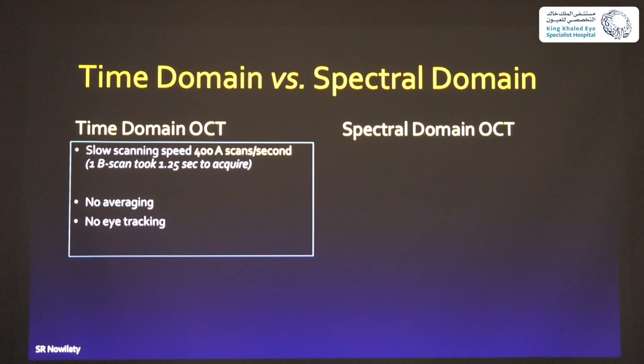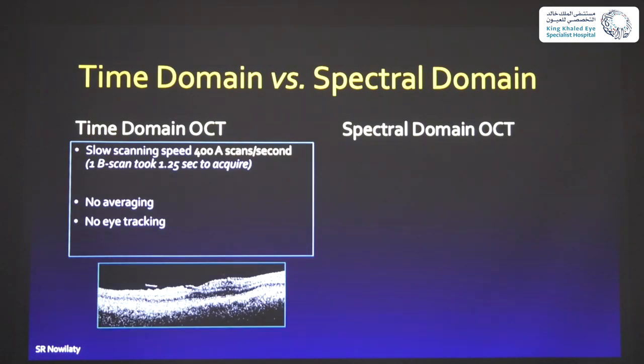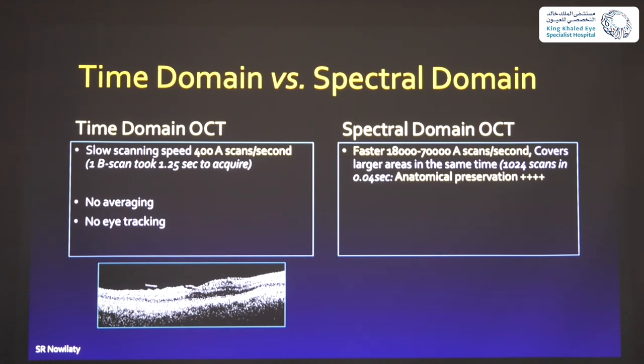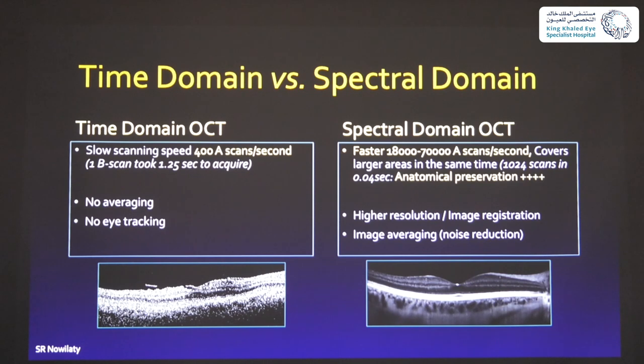In time domain OCT, you have a slow scanning speed; you can't get any averaging because every single B-scan comes in at a different place, and you can't do any eye tracking. In spectral domain OCT, all the B-scans are taken at once and the speed can go up to 70,000 scans per second, covering a larger area at the same time. Those images can be averaged together — meaning multiple cuts are taken and noise is removed, anything that doesn't repeat itself in the same cut — giving you a much clearer, crisper image.